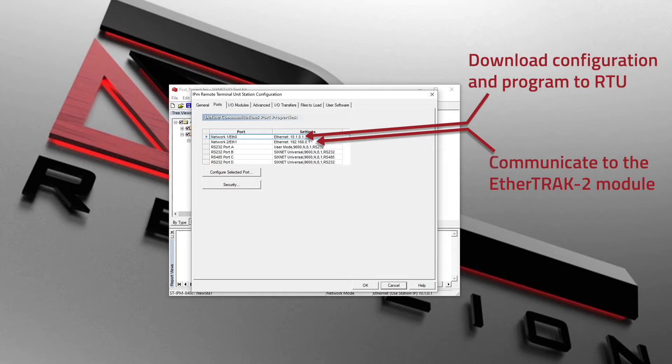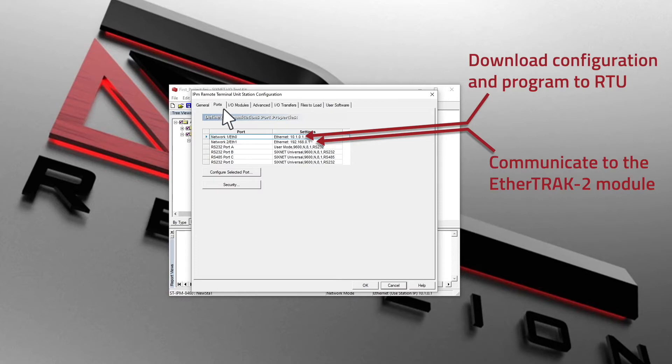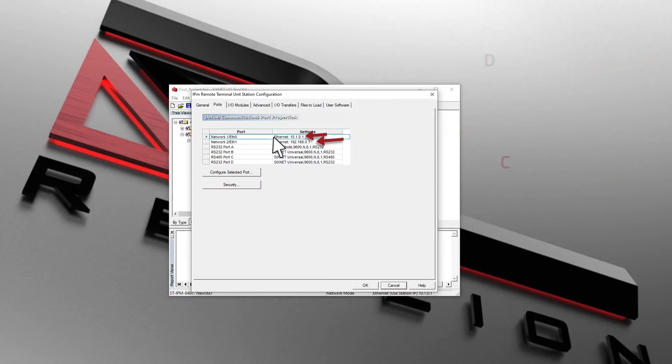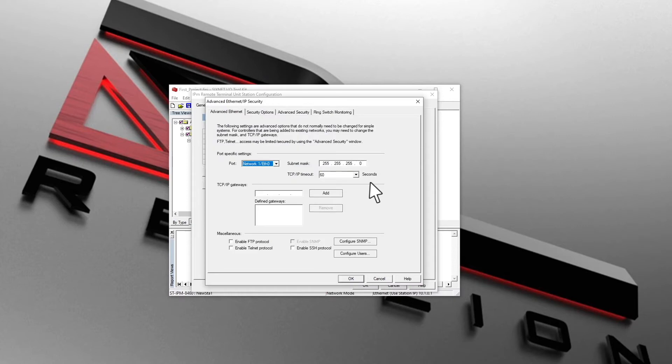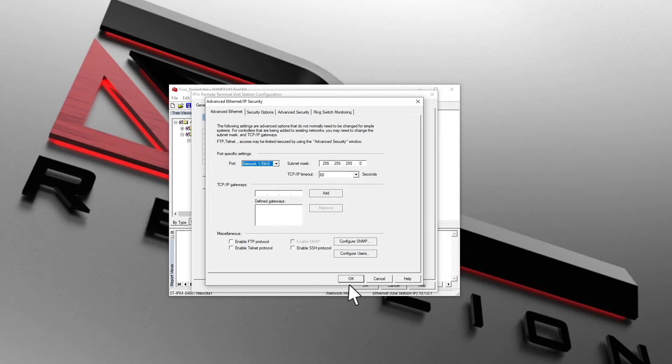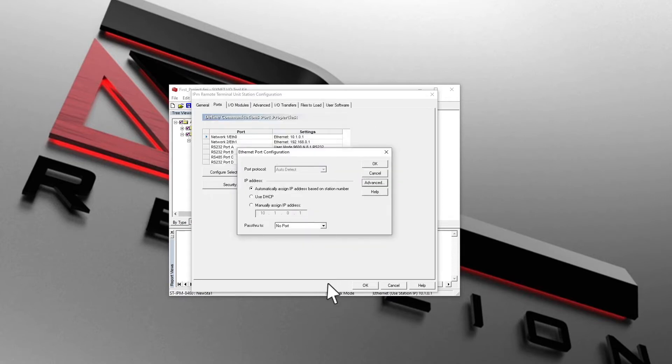Also note the IP address for interface 2 is 192.168.0.1. We will use this interface with its onboard switch to communicate to the EtherTRAK-2 module. Double-click on the IP address to configure it. Click on the Advanced button to configure the subnet mask for both interfaces. In this network, we will use Class C addressing.